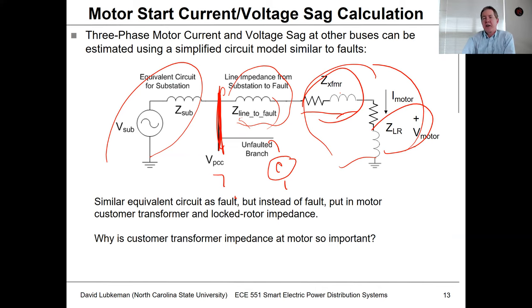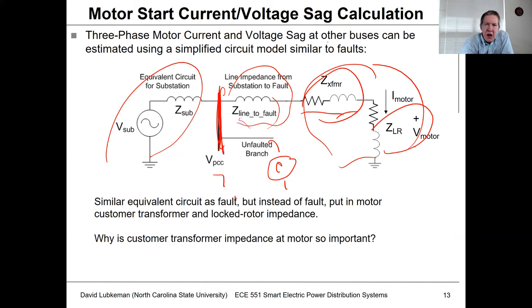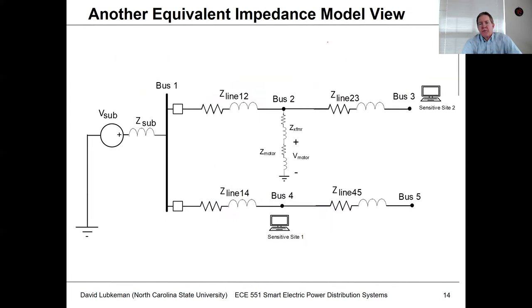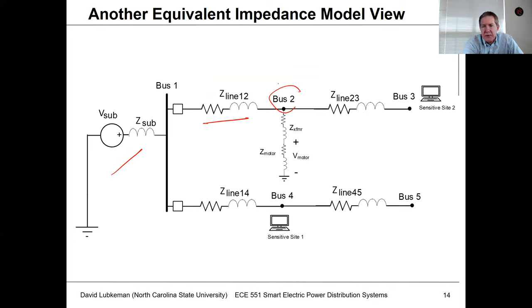In these calculations we're going to use per unit because we would have a transformation at the substation and at the customer, making it awkward to work through two transformations in volts and amps. In this equivalent view we have two parallel feeders: the substation, the line, bus 2 where the motor is starting, and we're interested in what degree a customer on the same feeder would be affected versus a customer on an adjacent feeder.